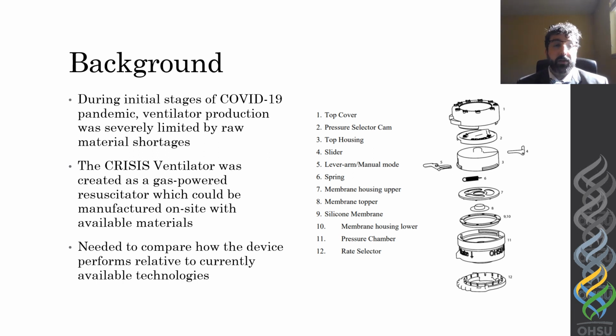Our device, the crisis ventilator, was created as a gas-powered resuscitator in response to this. The simple concept being that a 3D printed ventilator could be produced on-site using readily available materials. It consists of 12 individually 3D printed parts, which can be made on a fused deposition modeling hobby-level 3D printer, in addition to a silicone membrane and a spring that were readily available during the worst stages of the pandemic. One question for us, however, was how would this device compare to currently available technologies on the market?